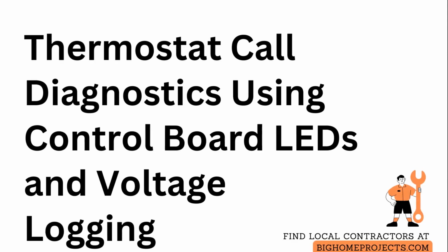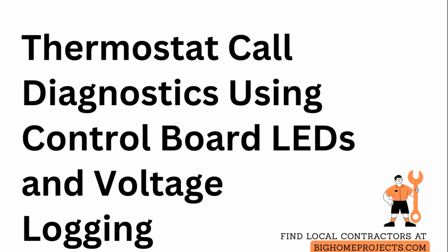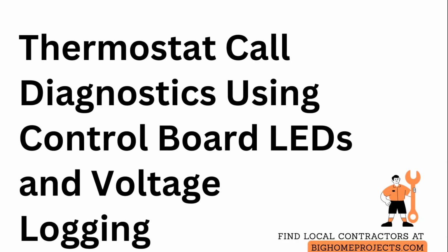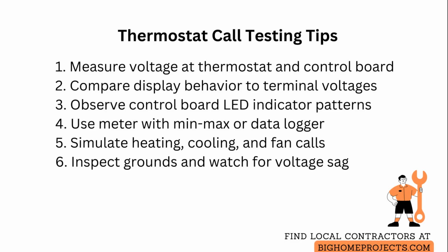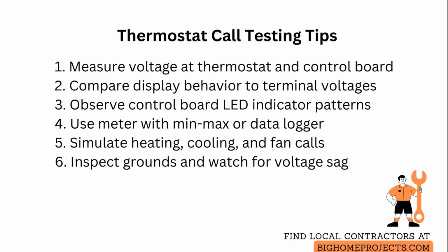Thermostat call testing requires focused observation to catch intermittent faults that otherwise slip through standard checks. When testing a thermostat call, monitor the control board light indicators and the voltage at the thermostat terminals while the call is made, because intermittent faults are often visible only in real time.